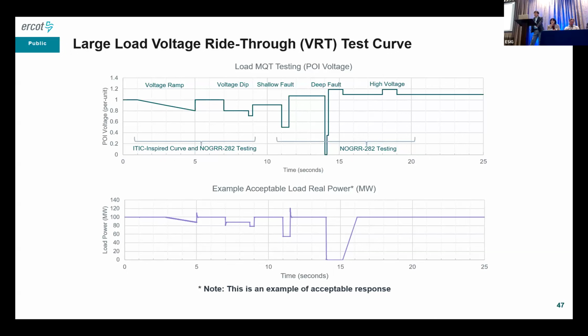At the bottom is an example of an acceptable load real power response. As you can see, they ride through and continue to consume power even at the low voltage conditions. And after the fault clears and voltage is recovered, the load comes back within two seconds. And on the high voltage condition, it continues to consume power at the pre-disturbance level.